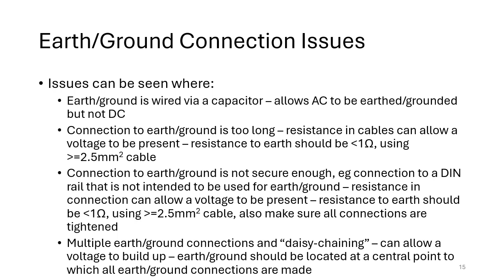Another option there is also to use star washers. Star washers are special types of washers that have connections on them that can actually make sure that you've got a better electrical circuit. Just connecting a wire to a DIN rail might not be enough to actually ground that DIN rail. You might get enough of a termination resistance there that you could still get higher voltages. So use of a star washer could give you some help there to make sure that that current is lower. But remember that DIN rail isn't necessarily intended to be used for earth or ground, so you might need separate earth and ground connections anyway going from your devices.